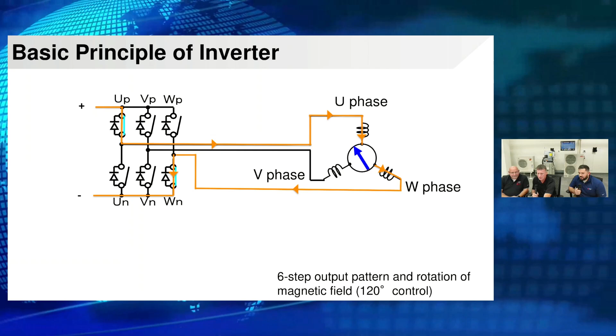So we did discuss this a little bit already, but when it comes to compressors, obviously you want to pull up the service specific, get the exact manual. Find your unit specific manual. Our service manuals will always have what ohms readings you should be getting. So depending on the size, you're going to ohm out across those windings, and resistance for those windings. Verify that you don't have shorts across windings. Checking for shorts to ground is no different than any other compressor. We're just going to use our megger, check for shorts to ground. So there's nothing out of the ordinary there. It's very straightforward when it comes to diagnosing compressors.